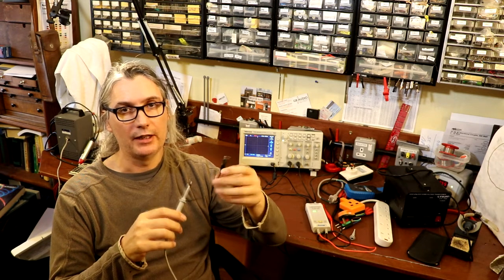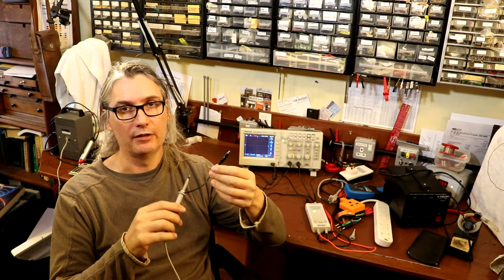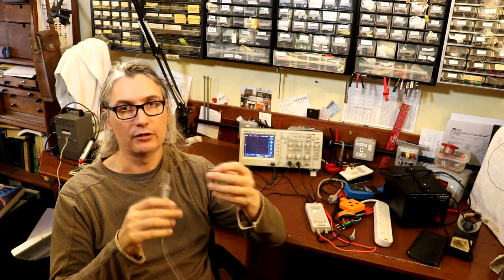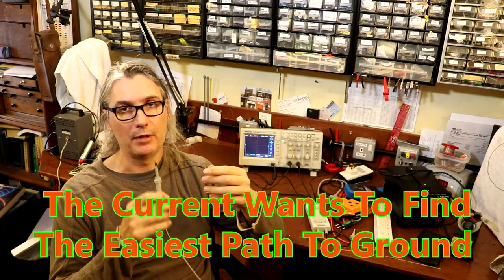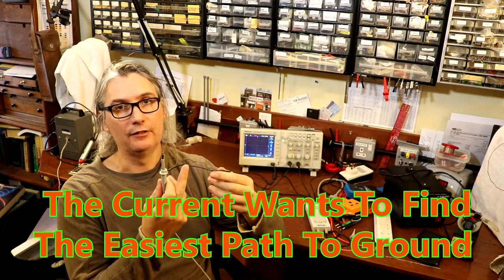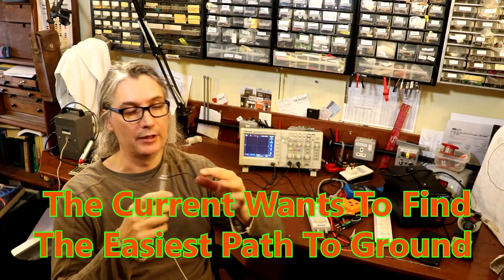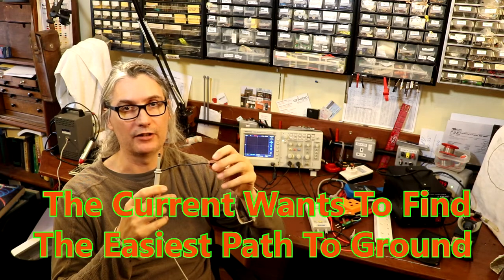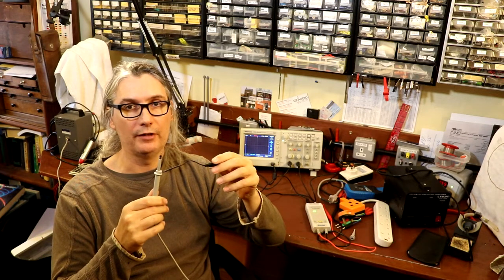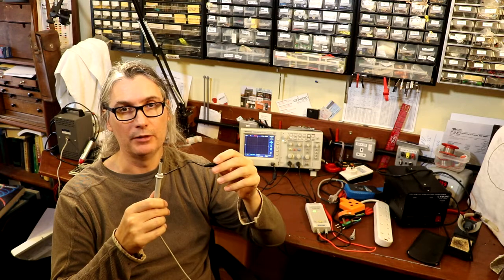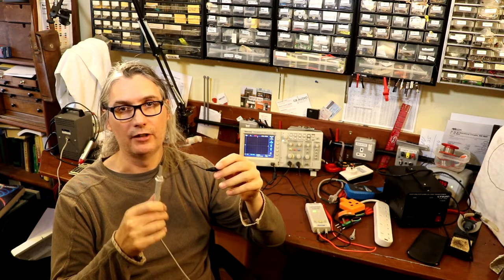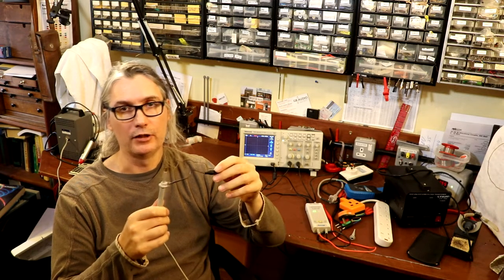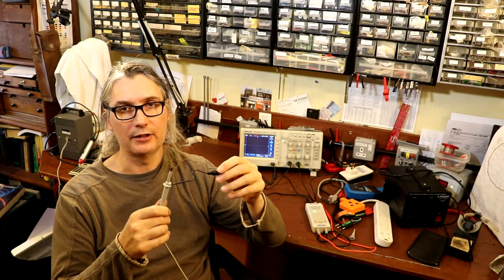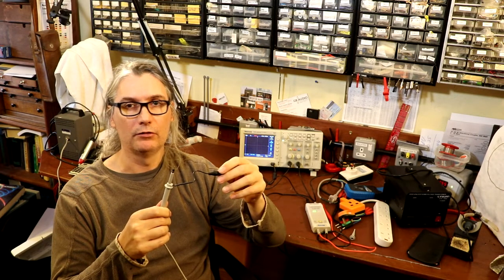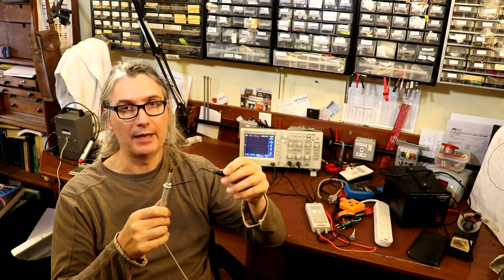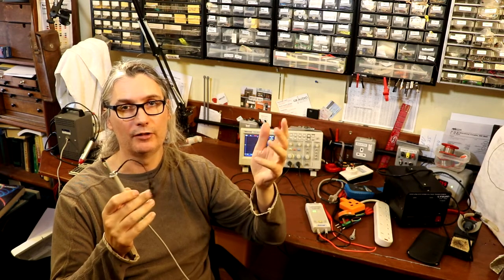So the problem is, if you clip on a scope probe, some of that current, rather than going through the neutral connection, will go through your scope probe instead. But the issue is that this is only a thin wire, so one thing that will happen is the wire will probably burn out — not good. The other thing that will happen, if you've got a fairly modern house with a modern consumer unit, is it'll detect that not all the live power is coming back down the neutral connection. It'll detect an imbalance and the residual current circuit breaker will trip, and all the lights will go off — so that's not very good either.